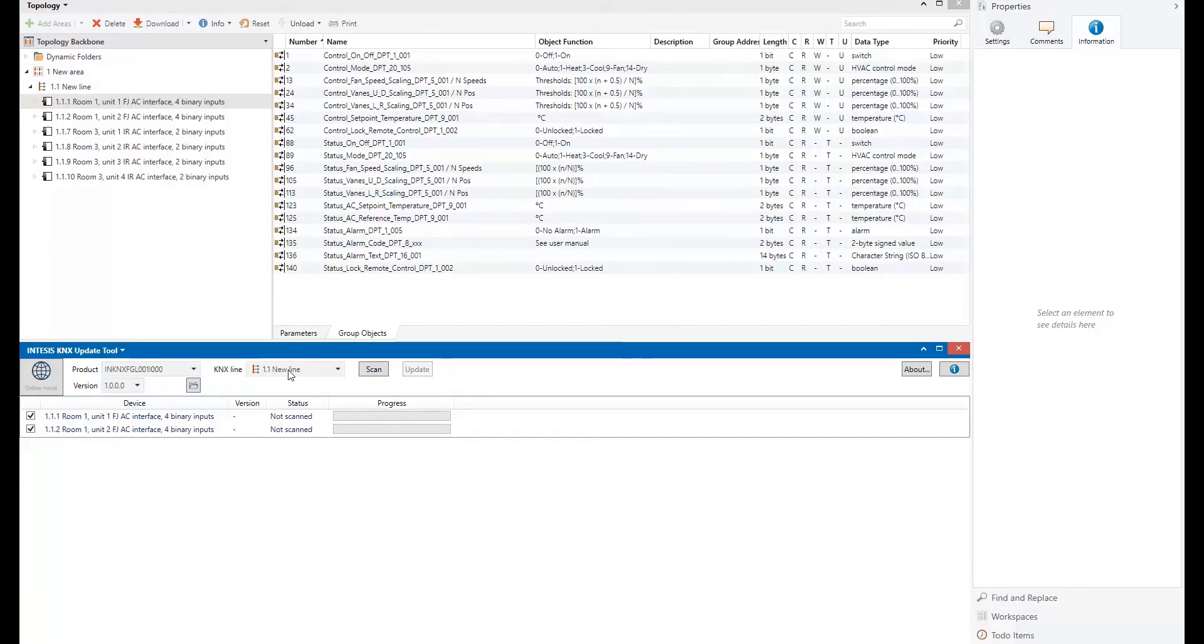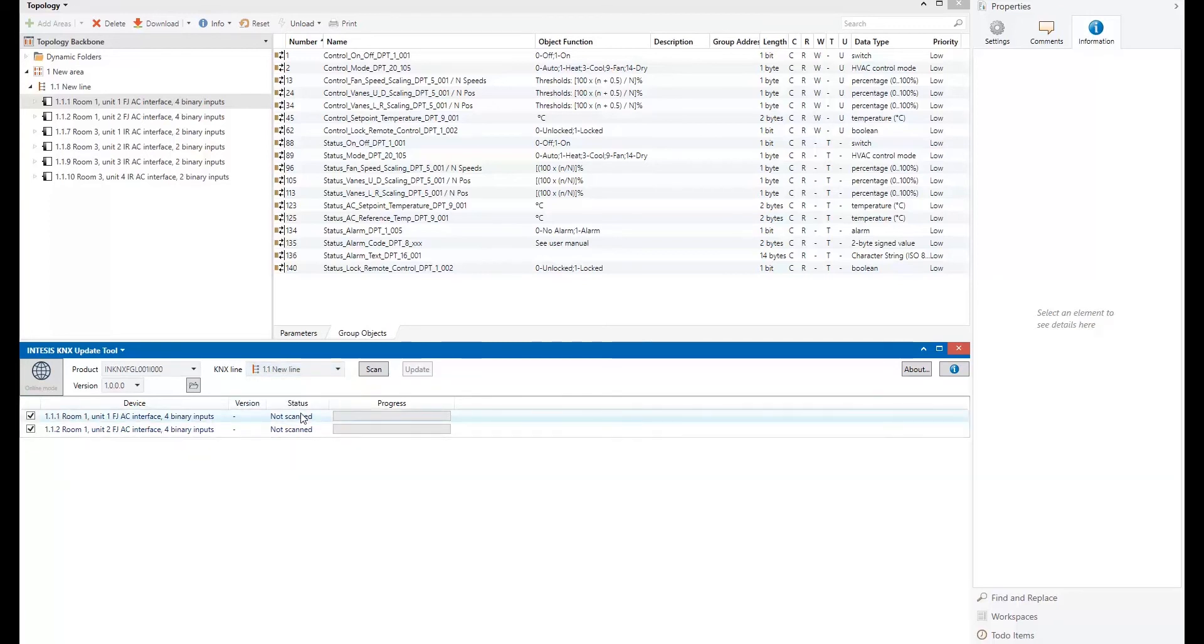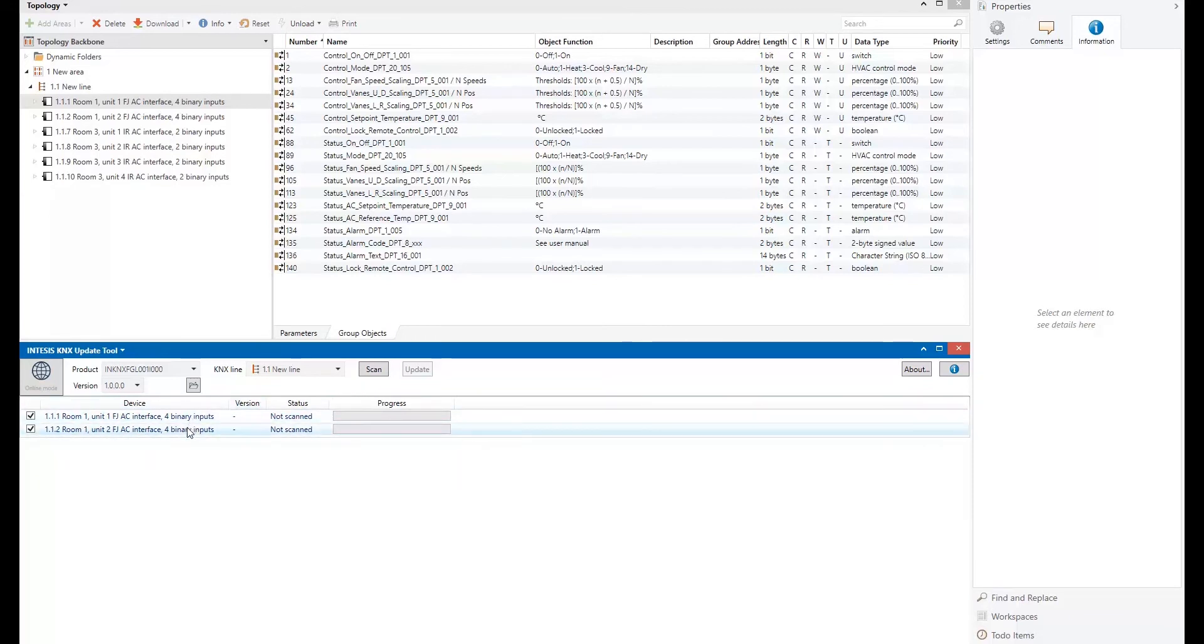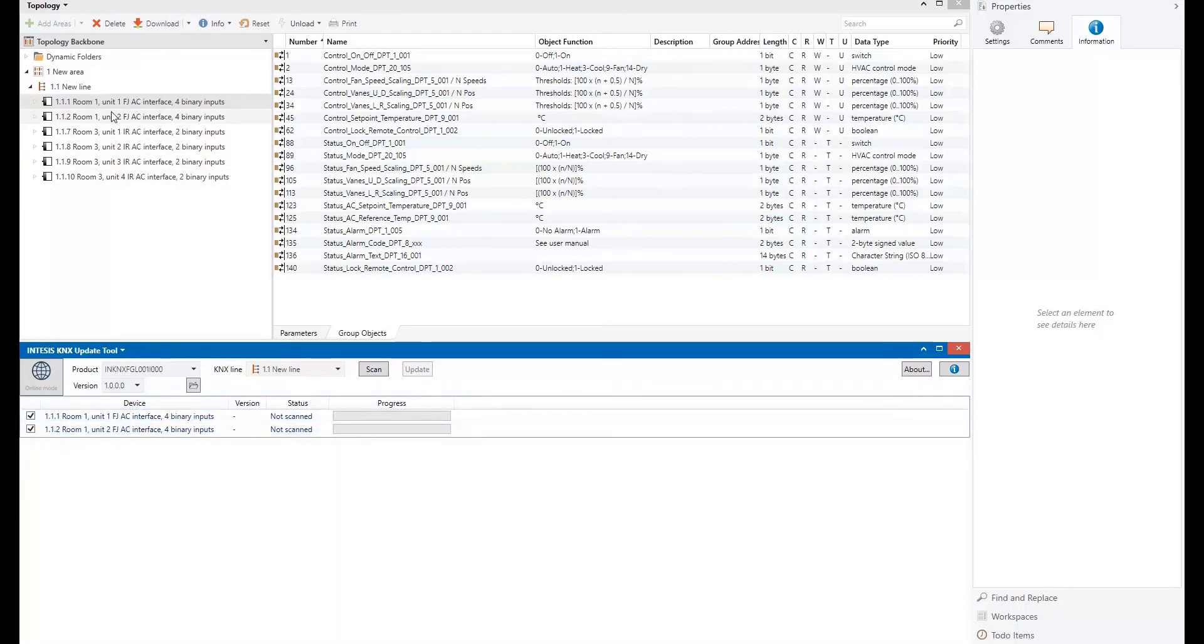the next step would be selecting the KNX line. Basically, my devices are located in the 1.1 line. So I will remain in that line. And till now, all the information, all the devices that we have here is retrieved from the ETS project. So basically, we are not still connecting or communicating with the KNX installation.